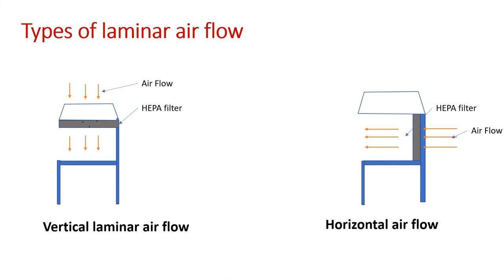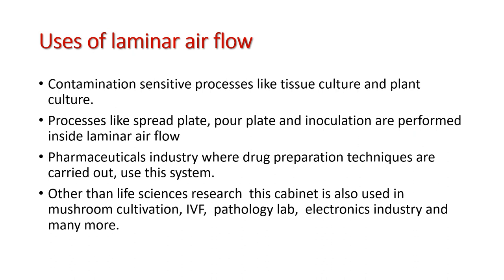Types of laminar airflow. The vertical flow cabinet is the most used type of laminar airflow. In vertical flow cabinet, room air enters the working area through a HEPA filter fitted on top of the cabinet. In the horizontal flow cabinet, air from the back side of the cabinet flows horizontally towards the user, creating a sterile working environment.